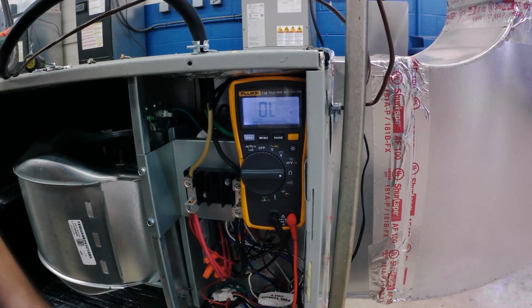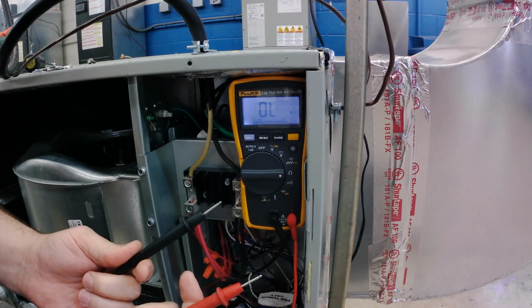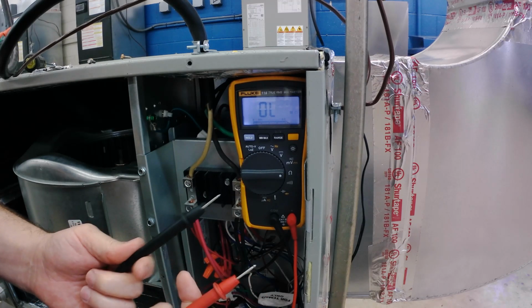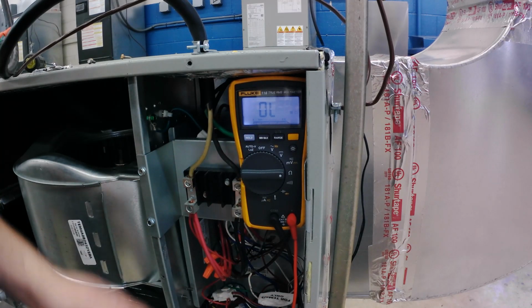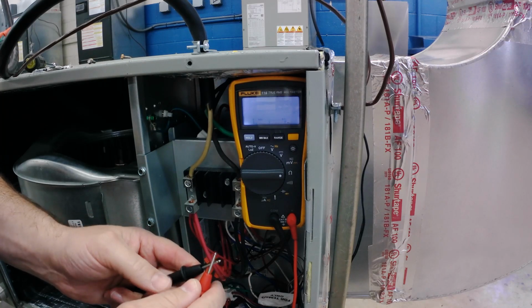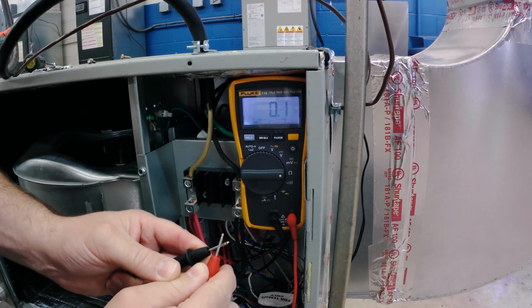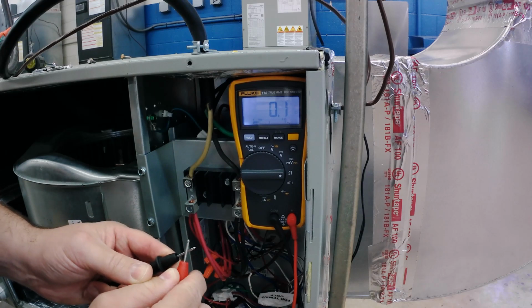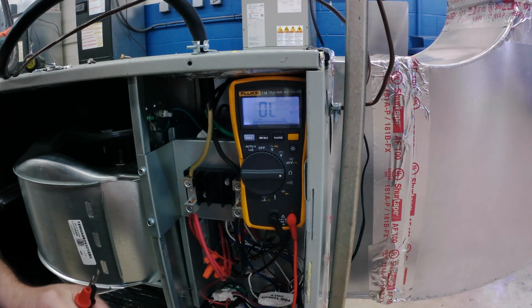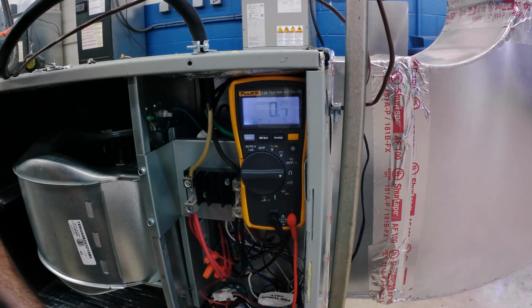If you see OL when you ohm out a coil, then what that means is this: there's nothing there worth anything between these two leads. OL is a bad reading. If you see 0, which is what you get when you basically put the two leads together, that means there's no resistance there. So you go to both far ends of the spectrum, either all the resistance in the world being OL or no resistance. Both of those are bad.